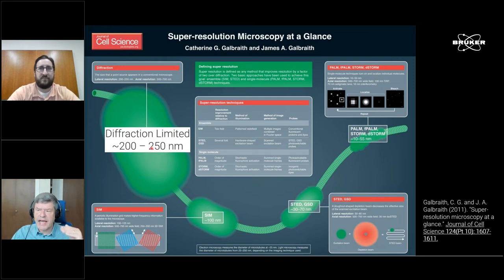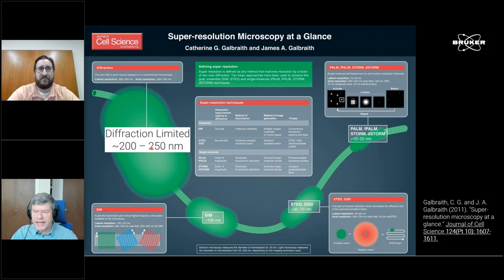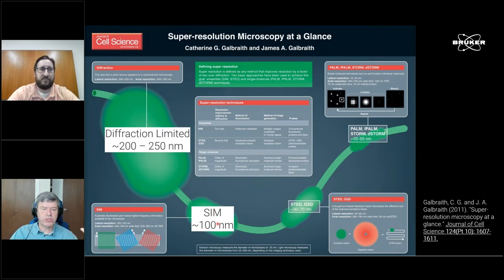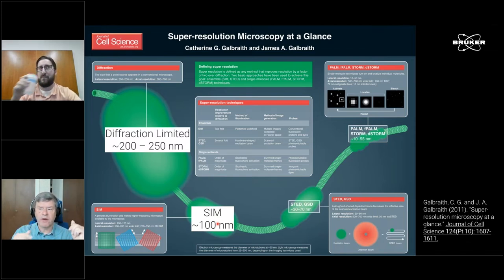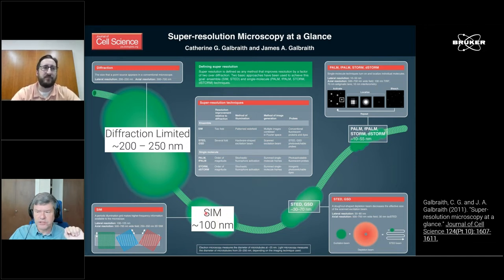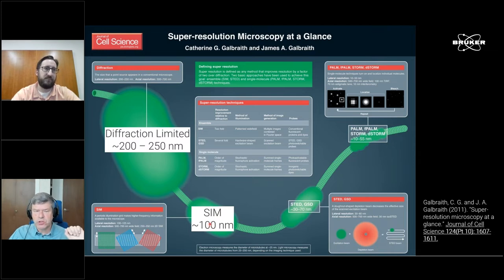That would be a very high-end diffraction-limited microscope. People always try to push the resolution, and that's where all the super resolution microscopes come into play. One very popular solution is structured illumination microscopy — that's the microscopy where you project patterns into the sample to amplify lower spatial frequencies. With structured illumination you can typically double the resolution, so about 100 nanometers, and if you add deconvolution on top of it, people claim you can get even a little bit better.